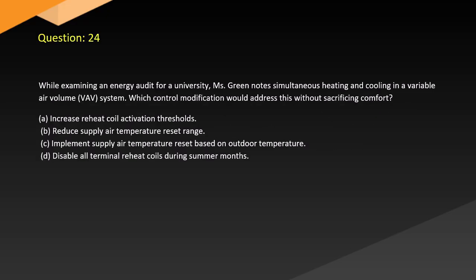Question 24. While examining an energy audit for a university, an engineer notes simultaneous heating and cooling in a variable air volume (VAV) system. Which control modification would address this without sacrificing comfort? A. Increase reheat coil activation thresholds. B. Reduce supply air temperature reset range. C. Implement supply air temperature reset based on outdoor temperature. D. Disable all terminal reheat coils during summer months.